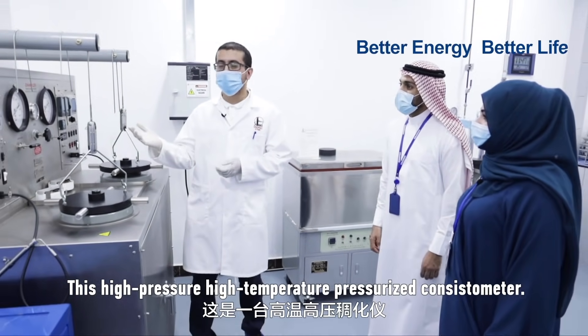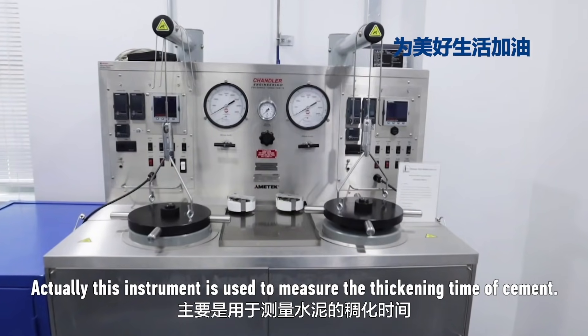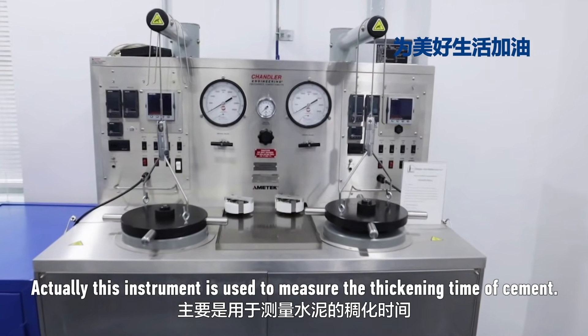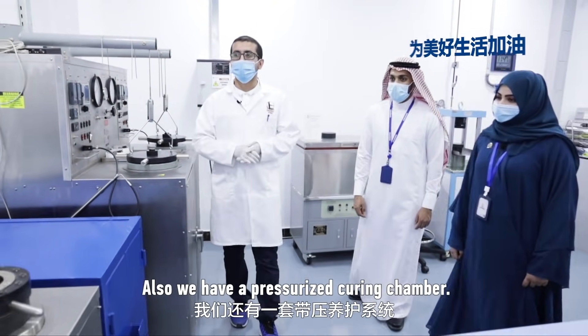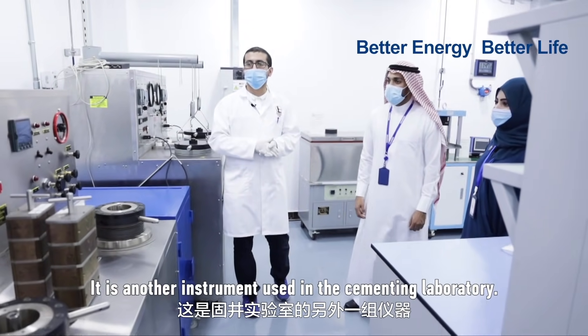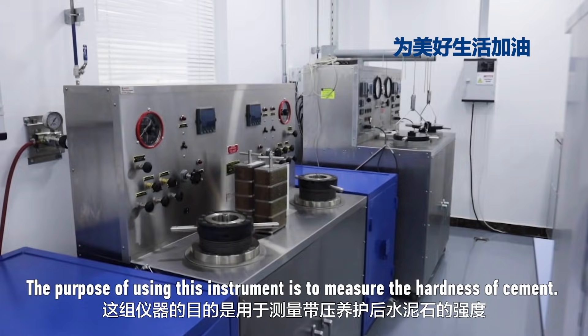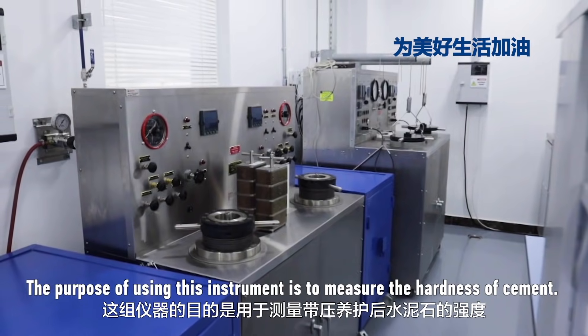This is a high pressure, high temperature pressurized consistometer. This instrument is used to measure the thickening time of cement. We also have a pressurized curing chamber — another instrument used in the cement laboratory. The purpose of this instrument is to measure the hardness of cement.